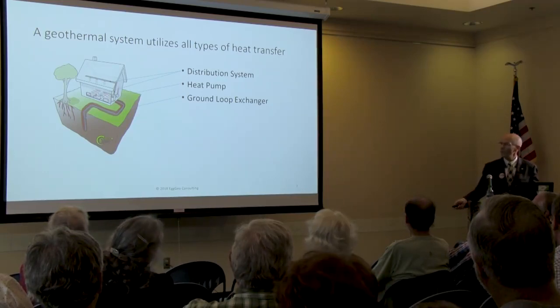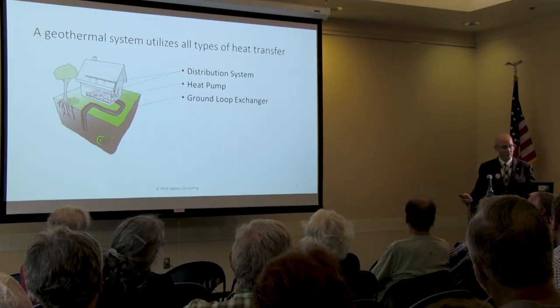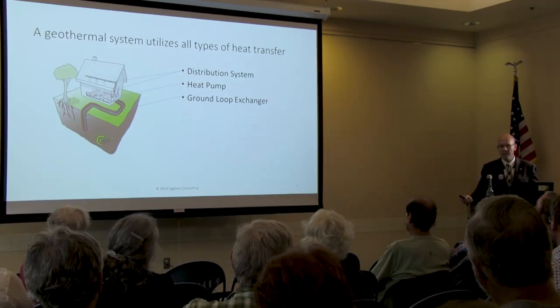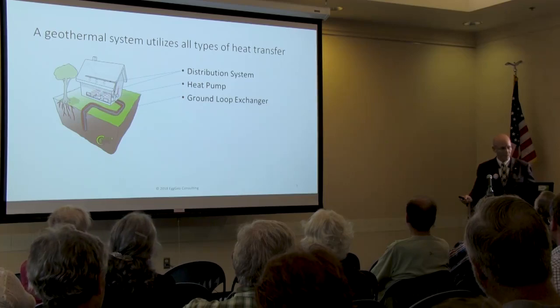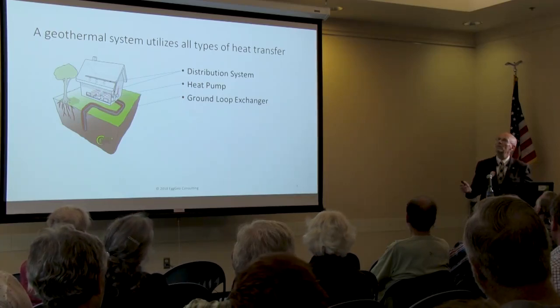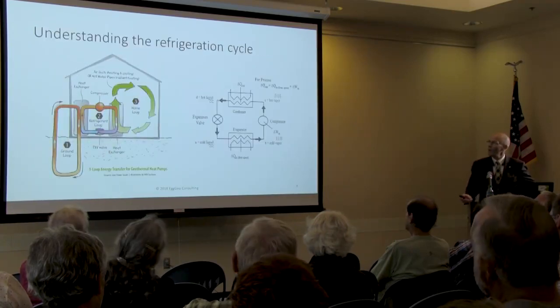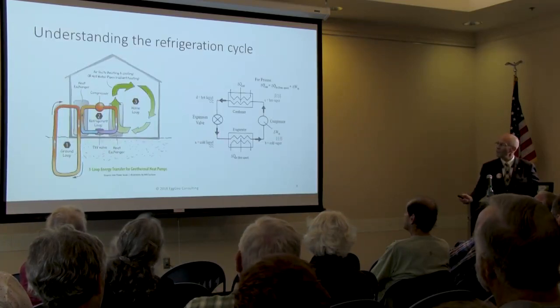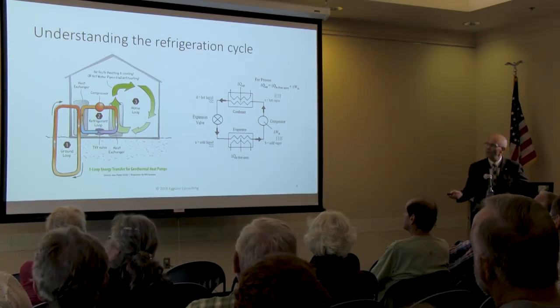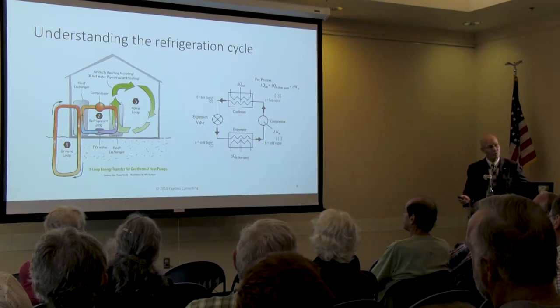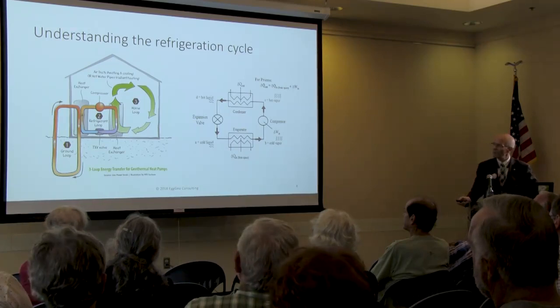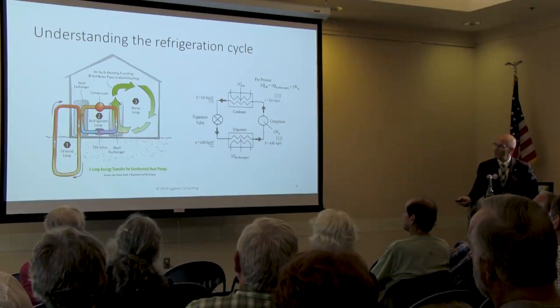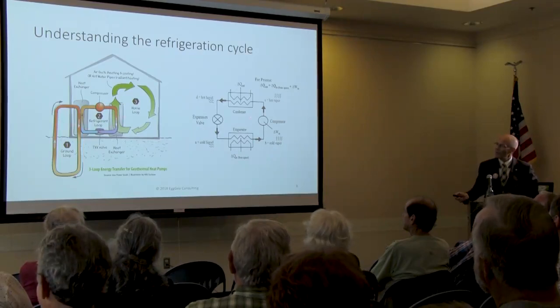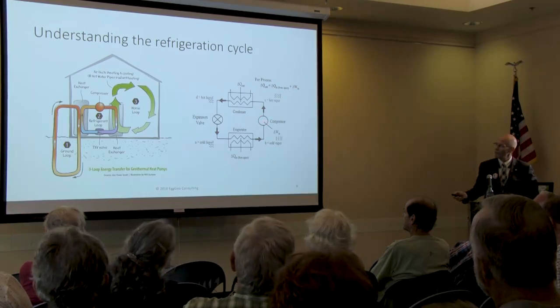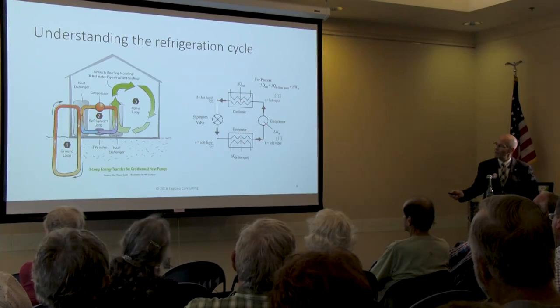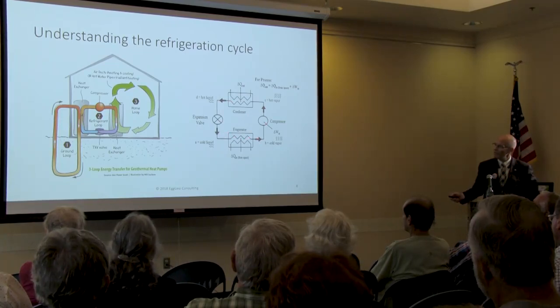Oftentimes, a building will have a radiant floor. There's radiant floor heating. There's also radiant floor cooling. I just wrote an article in Commercial Architecture about a big place in Toronto that has radiant floor cooling. But more common, there are radiant panels in the ceiling, too. The refrigeration cycle is important to understand for this because, as I mentioned, by and large, most geothermal heating and cooling systems use a heat pump. This heat pump is indicated right here in this simplified diagram, but every refrigeration cycle has a compressor, a condenser, an expansion valve, and an evaporator.